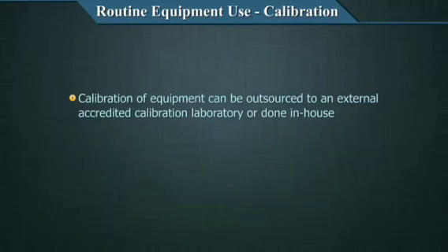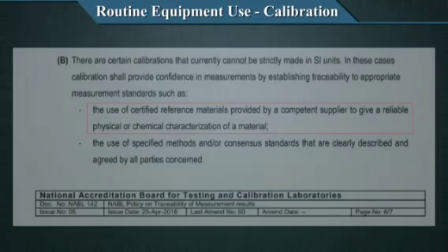This is what happens in most analytical equipment like your biochemistry analyzers, etc. A lot of your components like the lamp, cuvette, etc. are checked through the mechanism of just checking it. Because at this point, there are certain calibrations which cannot strictly be made in the SI units.